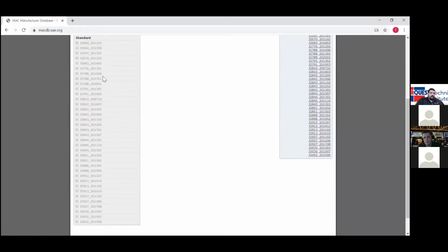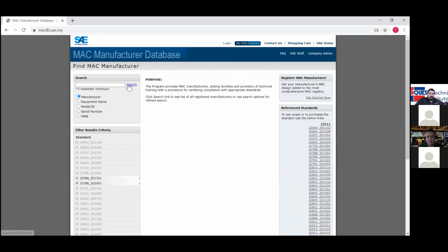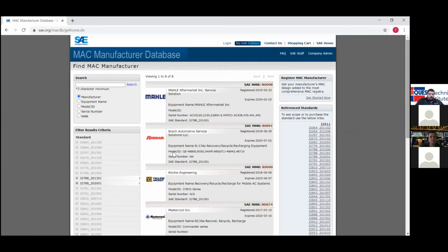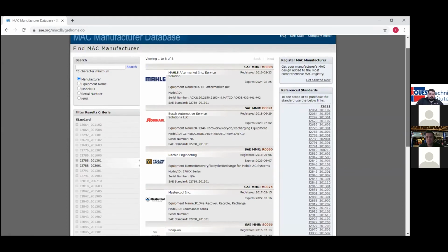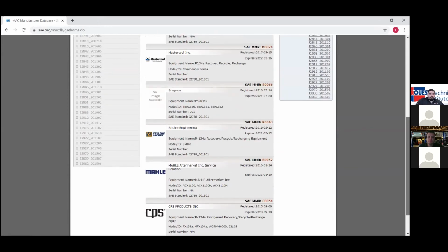So let's pick here J2788. That's the standard that governs an R134A refrigerant recover and recycle and recharge machine. You'll see there are two versions of the standard listed. We have J2788 2013-01. That means that's a version of the standard that was published in January of 2013, and now a new version that was published in January of 2020. So if I select these two standards, say I'm looking at buying an R134A recovery machine, and I click search, I will see every piece of equipment that meets one of those standards. We can see what standard that piece of equipment is certified to, name and part number, as well as when that piece of equipment was certified and when the certification expires. So you see all of that for an R134A recovery, recycle, and recharge machine.